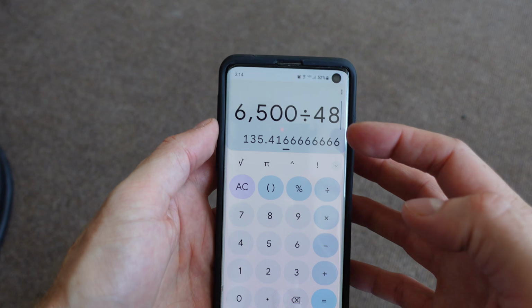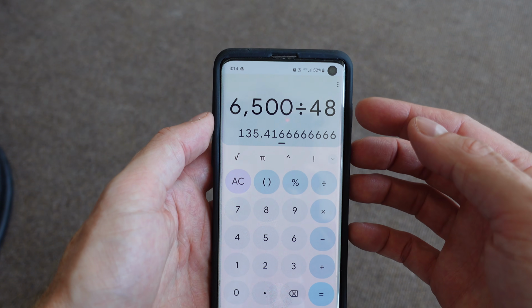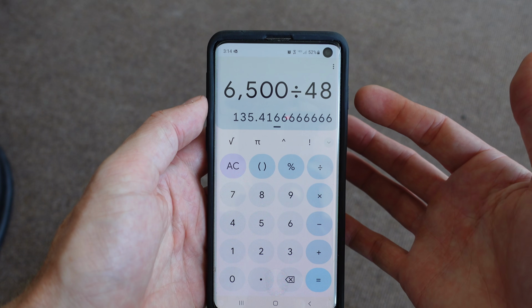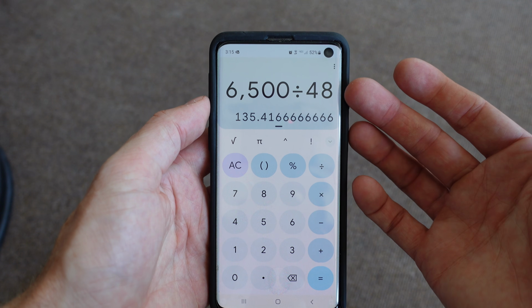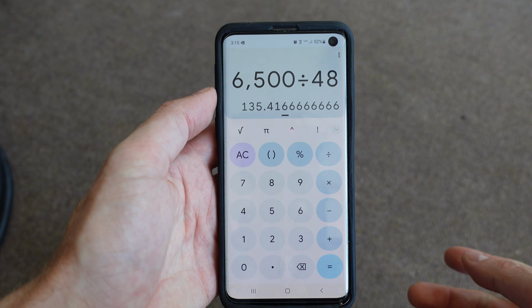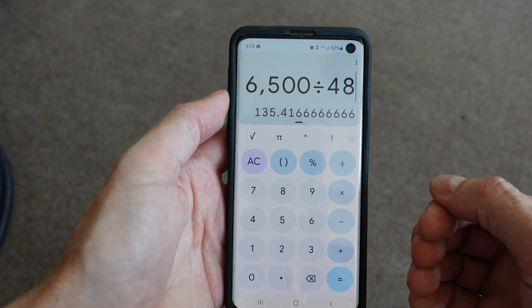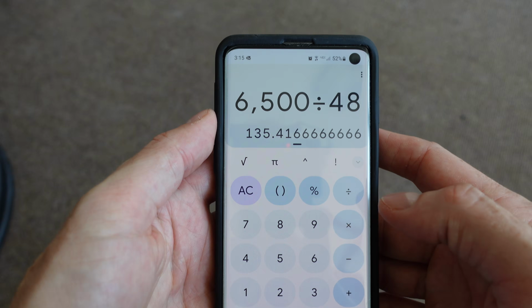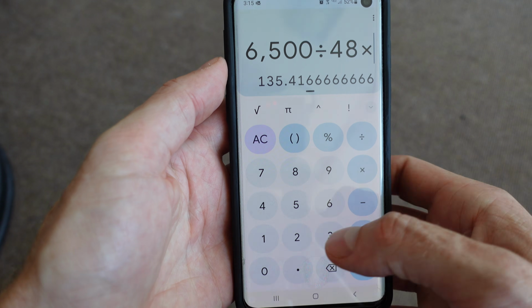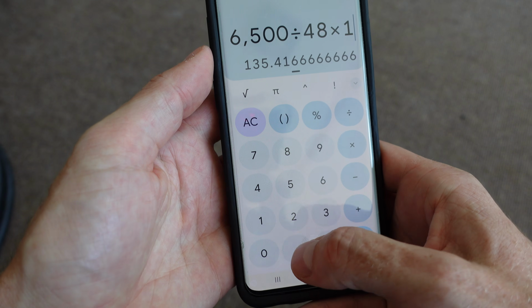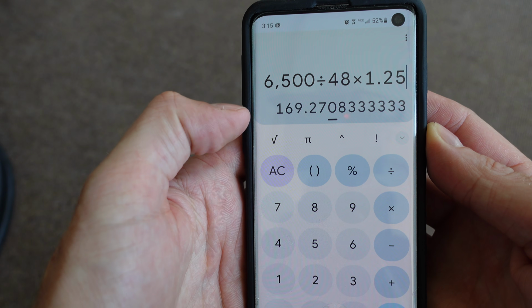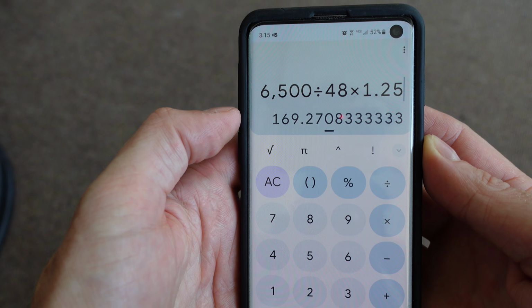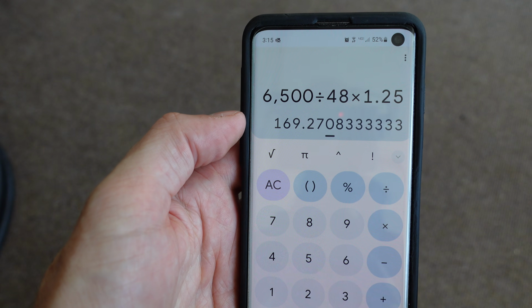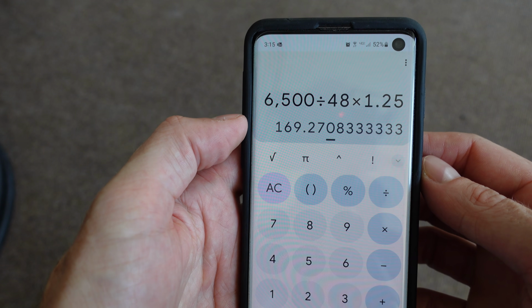So to get to that fuse size, I have 6,500 watts divided by 48 volts. This is the nominal voltage, so it will go a little bit lower than this at the end of state of charge. But we're going to use this for the calculation. And then in overcurrent devices, we typically derate to 80% for a continuous load. So I'm going to multiply by 1.25. So that gives us a fuse size of 169 amps. And then we'll round up to the most commonly available size of 200 amps for this use case.